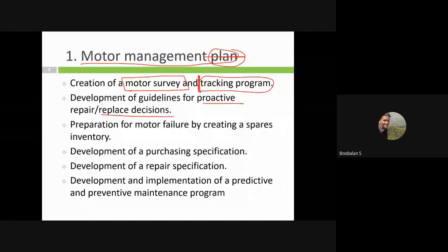For that purpose, we need to make a decision. By doing this survey and tracking, we can decide whether to repair the motor or replace the winding. By doing monitoring and measuring, we can make proactive decisions about whether to replace the motor with a new one or just replace the winding. These decisions happen once the survey and tracking process is complete.